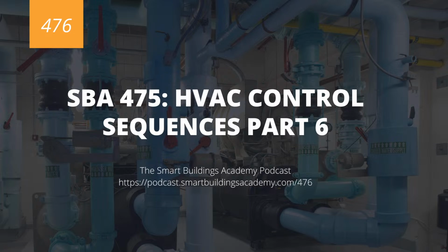We need to make sure that we have water flowing, that systems are enabled, that pumping's enabled. And so I have this sequence that I've used time and time again, and it's been really beneficial for me and has really helped me to make sure my chilled water sequences and programming operate pretty much optimally and are very easy to troubleshoot. It starts off with system enable.